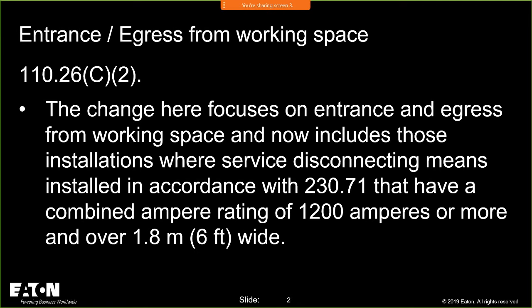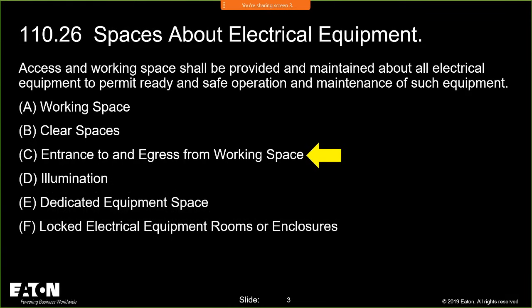They made a change to that because now they're saying, look, it's not whether or not that one overcurrent device is 1200 amps and above. It's really about the amount of energy you have in that room. So it's an addition of the handles of all of those. This is really going to hit your design guys. From a design engineering perspective, this is commercial and industrial. This is something you're going to have to really pay attention to, especially on your next projects.